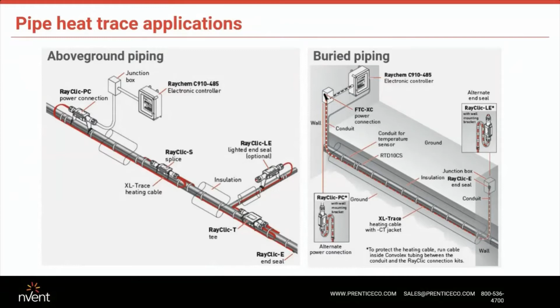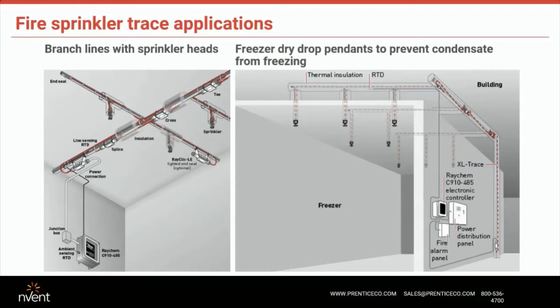For fire sprinklers, we are approved to do fire sprinkler systems to protect them from freezing. The typical applications I'd recommend solving with heat trace are smaller areas, like a small unheated garage, or a freezer where you have pendants dropping down into the freezer space. Those are all very good applications we can help solve. One thing to note is we do need a controller that does monitoring, so you have the capability of providing an alarm back to the fire panel to meet code.